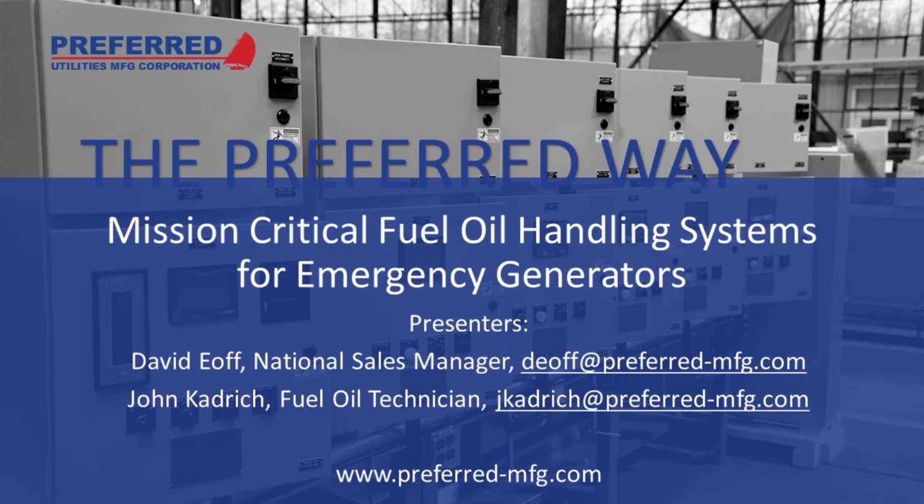John, how often do you see flow switches at the day tank fill manifolds? Probably about a quarter of the time. Okay. The thing about those flow switches is you don't want to have them outside where it's going to get rained on, because if water gets in the top of those flow switches, the electronics in there, the reed switch will fail. Oh, I got it. Yeah, if you can keep them inside where they're protected in an enclosure or something, they work way better.